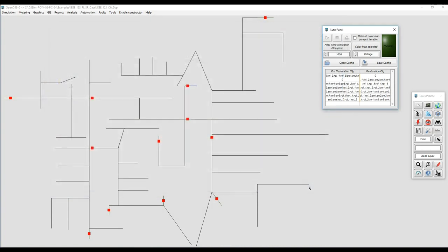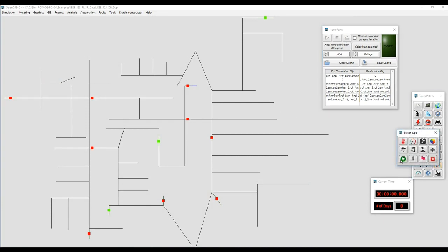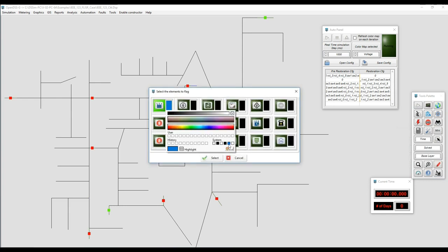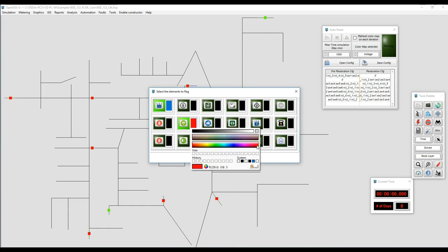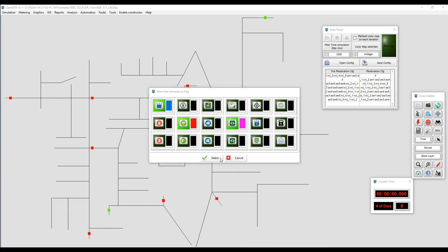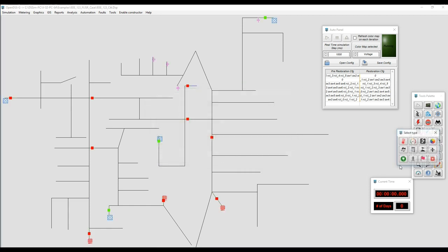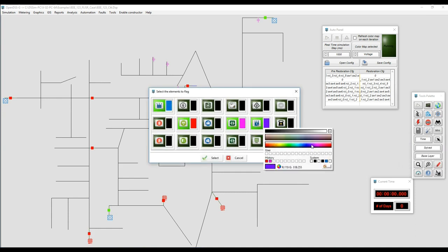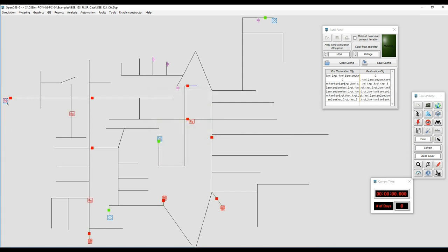We're going to load it up, and we're going to bring the system to the initial conditions. So as we can see, I'm going to bring the icons to make it more visible. We're going to bring the substations and the ties to other feeders, PV systems, cap banks, and also the regulator locations. So now we have them all. You can see we have 4 regulators, one 3-phase at the feeder head, and others individually per phase across the feeder. So now we're going to show the voltage.